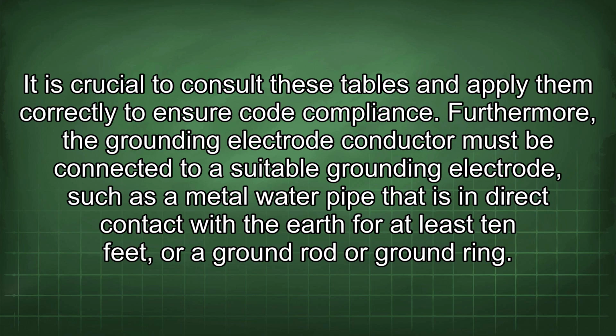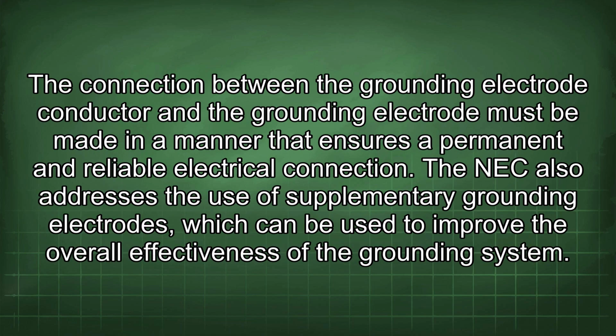Furthermore, the grounding electrode conductor must be connected to a suitable grounding electrode, such as a metal water pipe that is in direct contact with the earth for at least 10 feet, or a ground rod or ground ring. The connection between the grounding electrode conductor and the grounding electrode must be made in a manner that ensures a permanent and reliable electrical connection.